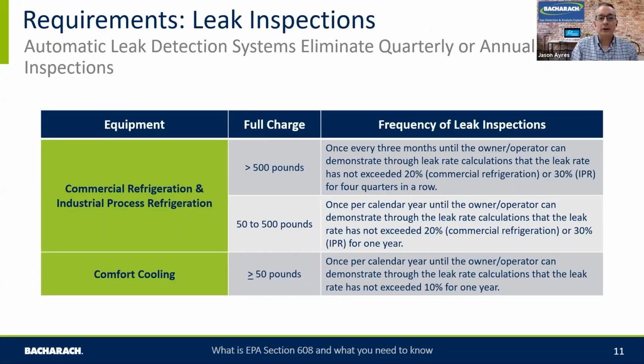So what is a leak inspection? Leak inspection is very simply a check on the system for checking it for leaks. And that's the entire system. So if you've got an asset that now falls under the leak inspection criteria, you have to do additional checks on that equipment. And those checks vary from every 3 months to a calendar year, depending on 2 criteria. One, the equipment bracket that it falls under, and the amount of refrigerant that system holds. Not how much it's lost, but how much it holds.